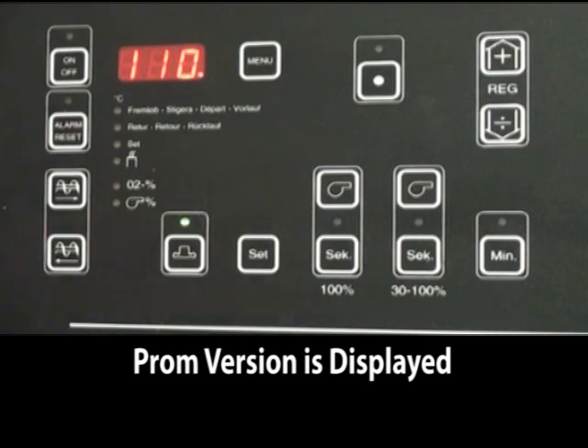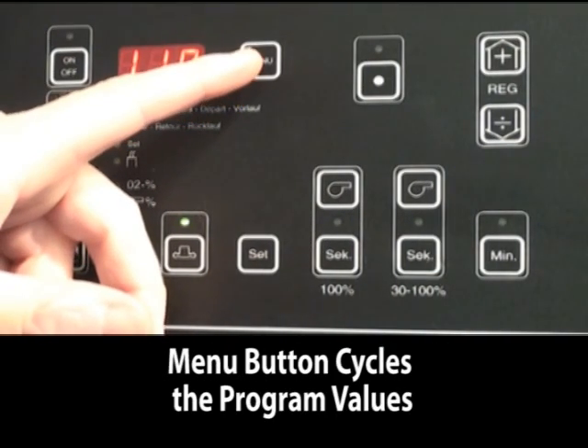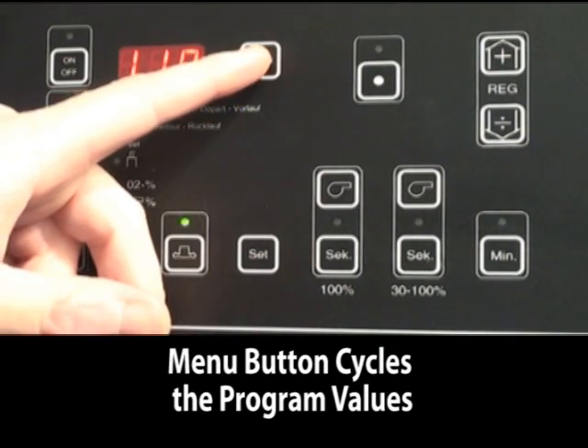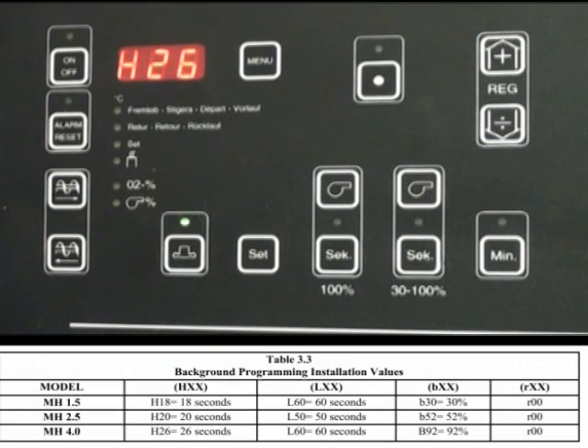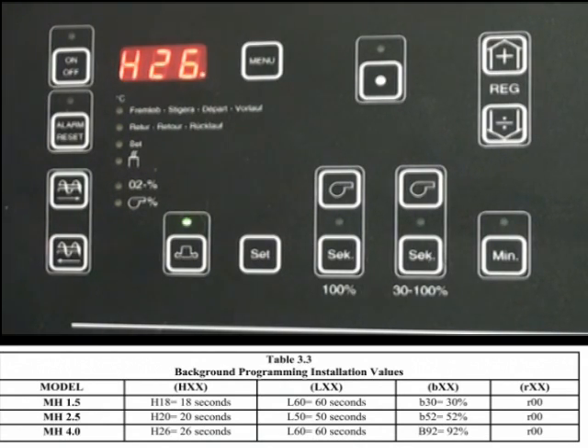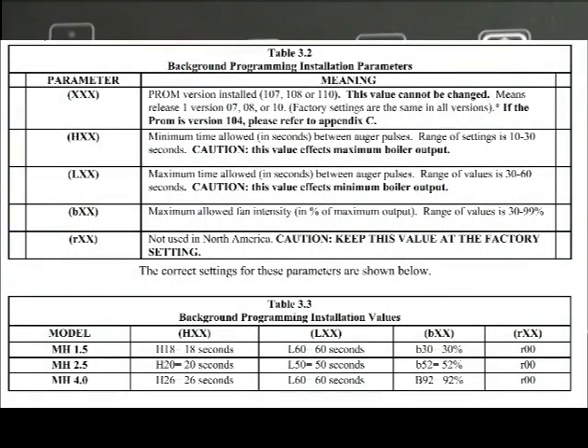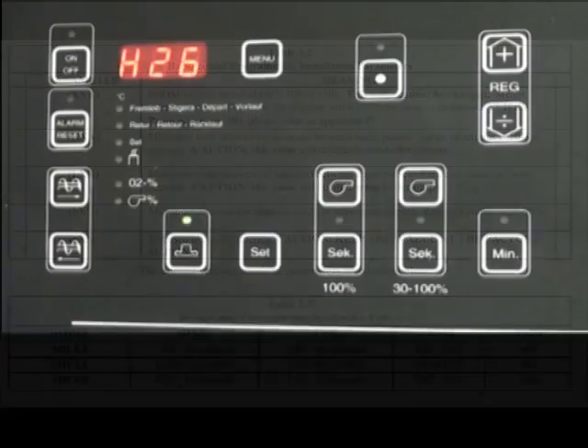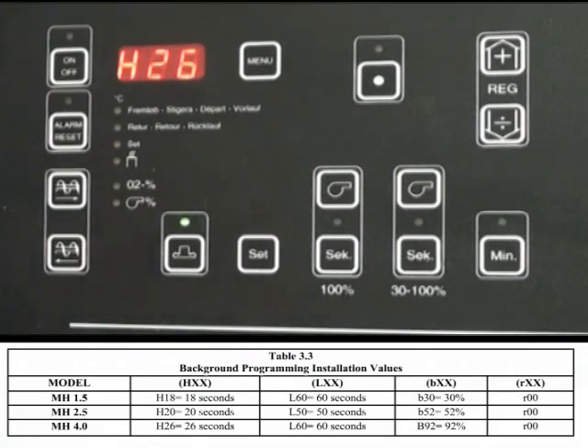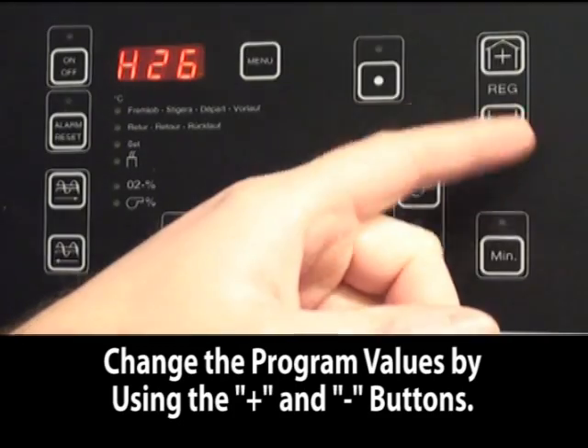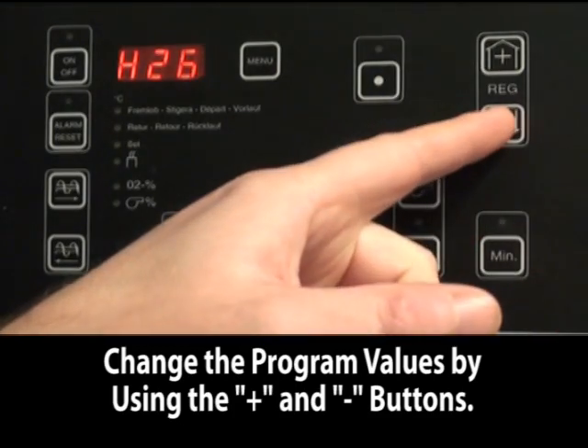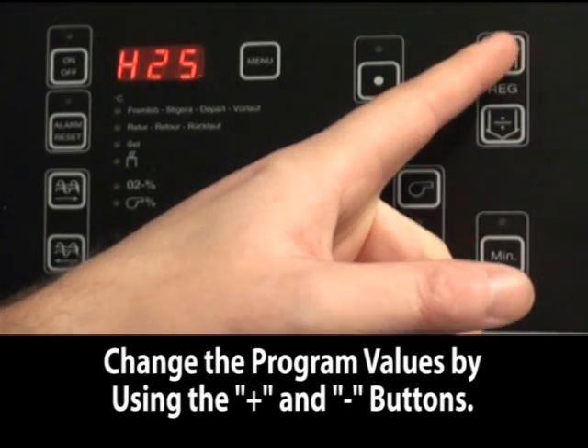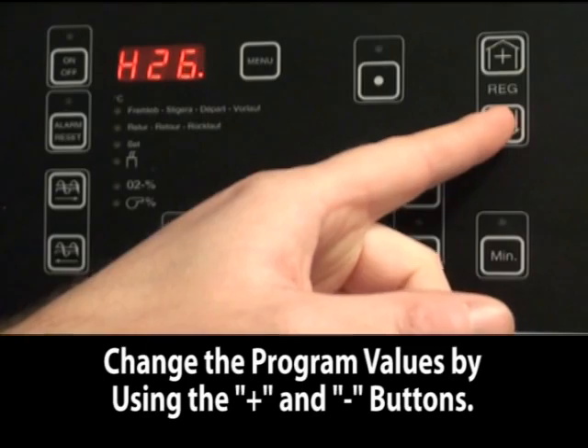Next, use the menu button to cycle through the menu. The first setting is for minimal time allowed in seconds between auger pulses. All of these settings are located in the manual. This setting should be either 26, 20, or 18 seconds depending upon the model of the boiler. If a setting needs to be changed, use the plus and minus buttons to change the setting.